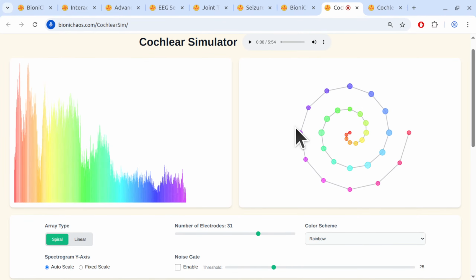But it seems to be about signal fidelity, basically, how true the output sound is to the original, without adding distortion or losing details. Faster WDRC can sometimes distort subtle timing cues in speech, making it sound a bit less natural. However, when you have strong DNR working hard, it's already cleaning up the noise before the compression stage. So it effectively kind of buffers or tempers the distortion that the faster WDRC might otherwise introduce. So the strong noise reduction makes the fast compression sound better, clearer. Exactly. Makes it more tolerable, and in that context, actually preferred. The DNR cleans things up first.